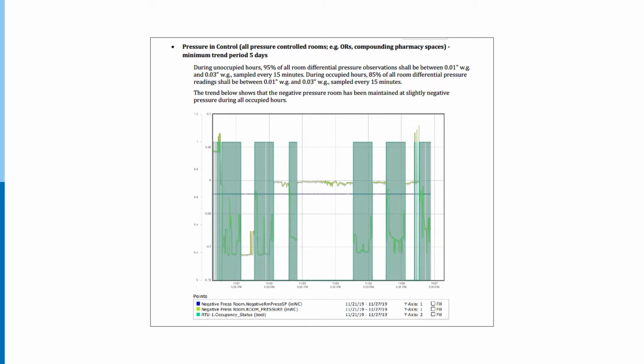And you can kind of see the trend of pressure here. It fails the criteria. What's kind of weird is that it looks like it complies or even over complies during the unoccupied periods, but most of the days, during the day, this looks like it's not meeting our acceptance criteria at all.